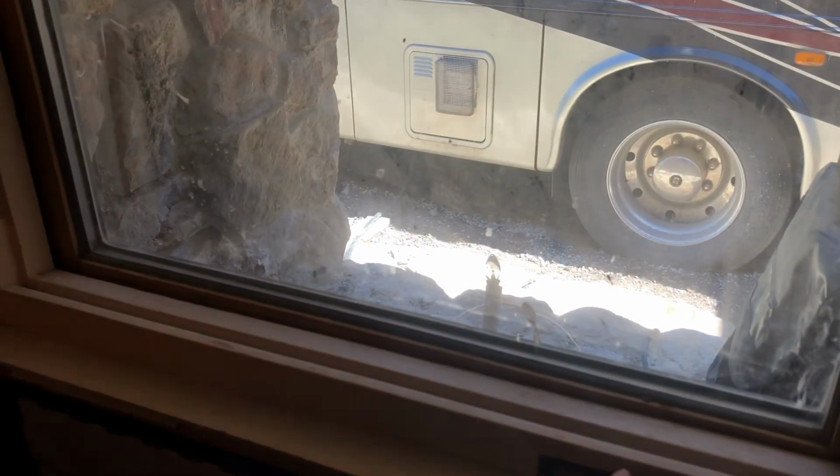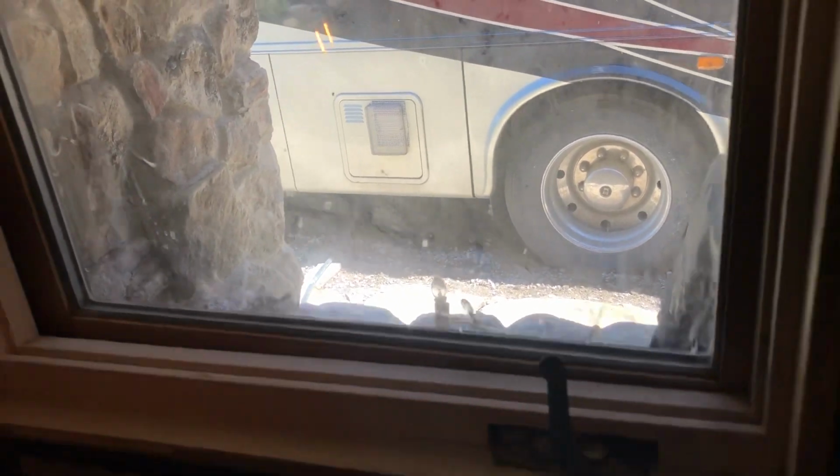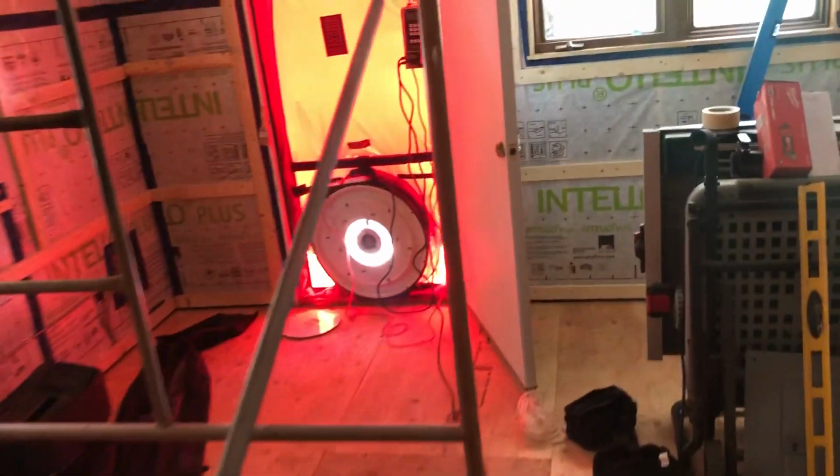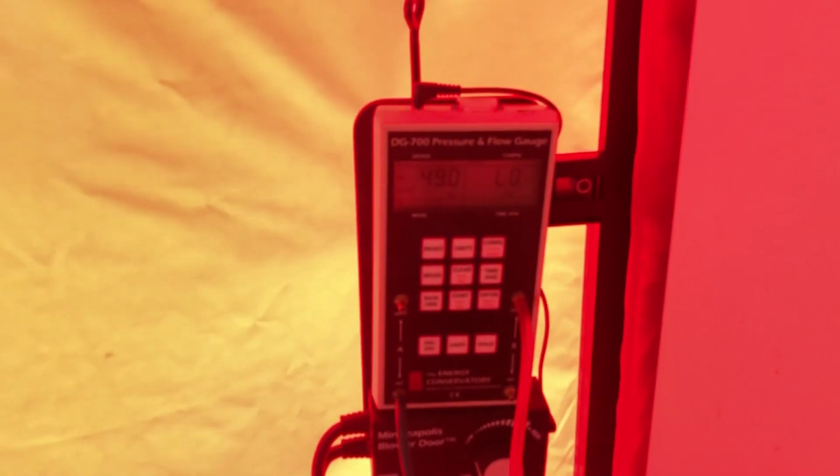It didn't keep reading. Anyway, this is what I'm working on today, and I'm really glad the building is nice and airtight. I have leaks right in the places that I thought I had leaks. Yeah, I bet it's 100 CFM is the minimum. So we're about 111 right now with that window open.